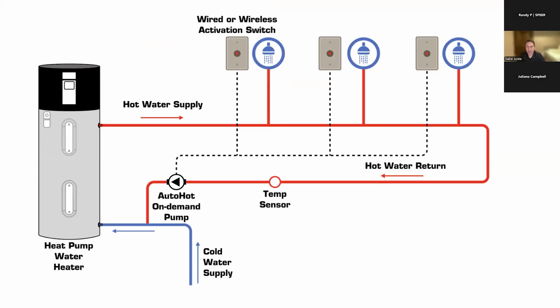Okay, so let's look at a typical recirculation loop configuration, and we'll go through the sequence of operation. So you have a little activator, maybe inside of the kitchen and the bathrooms, maybe somewhere outside of those areas. But basically, number one, demand is sensed by the occupant, and then anytime the control senses that, it's going to check the temperature of the return line or the end of the plumbing line, after the last plumbing fixture.